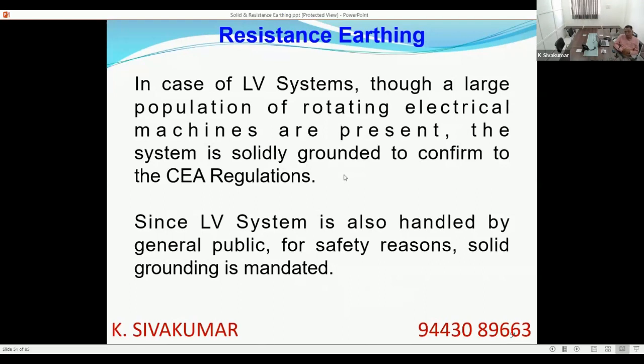In case of LV system, though a large population of rotating machines are present, the system is solidly grounded to conform to the regulations and standards and codes. Since LV system is also handled by general public, for safety reason, solid grounding is mandated, because in solid grounding, you do not need a dedicated earth leakage relay or ELCB or RCCB. The overcurrent device or the short circuit device itself will blow and protect, open and protect. If not, maybe human protection people may not mind. At least to safeguard their equipment, anybody will go for a fuse or a breaker to safeguard their equipment. So in solidly grounded system, such a device provided to protect the equipment will automatically isolate the fault and protect the people also. So that is the reason for recommending and mandating solid earthing for LV system.